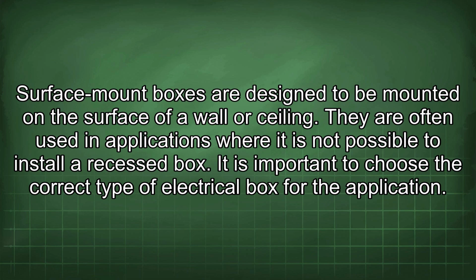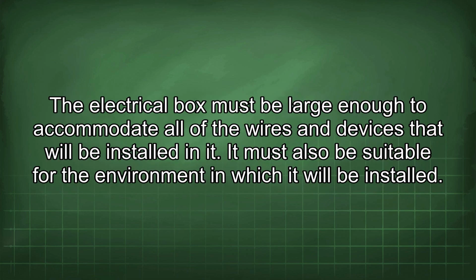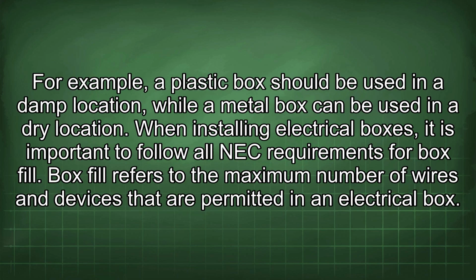It is important to choose the correct type of electrical box for the application. The electrical box must be large enough to accommodate all of the wires and devices that will be installed in it. It must also be suitable for the environment in which it will be installed. For example, a plastic box should be used in a damp location, while a metal box can be used in a dry location.